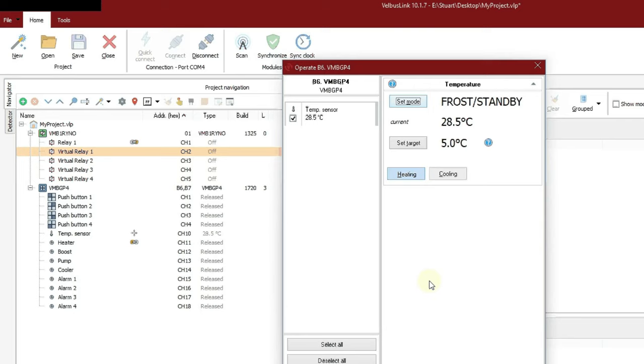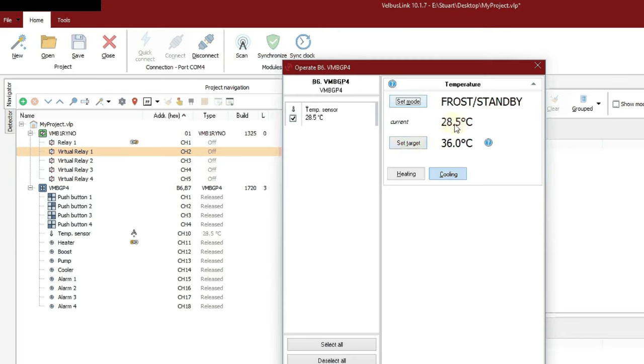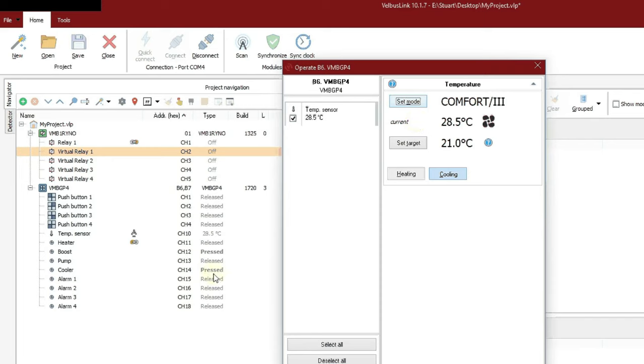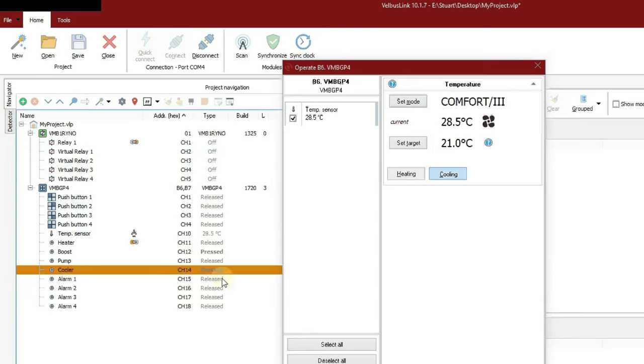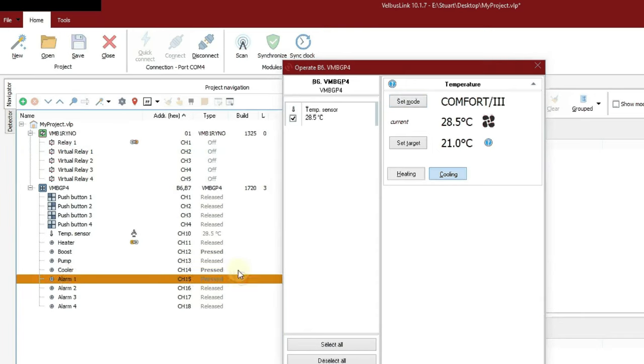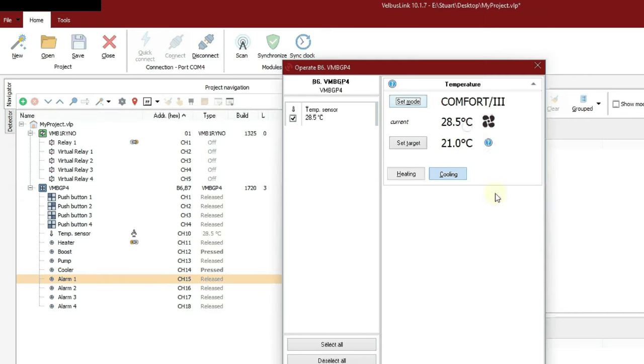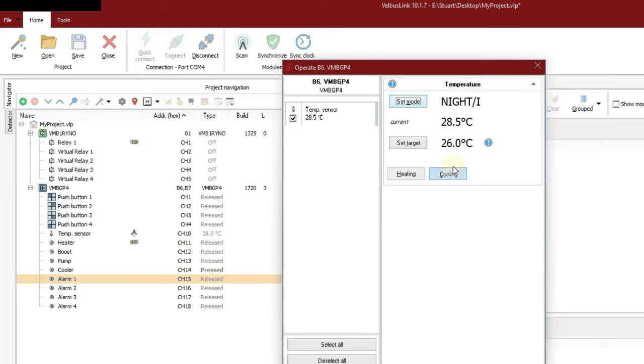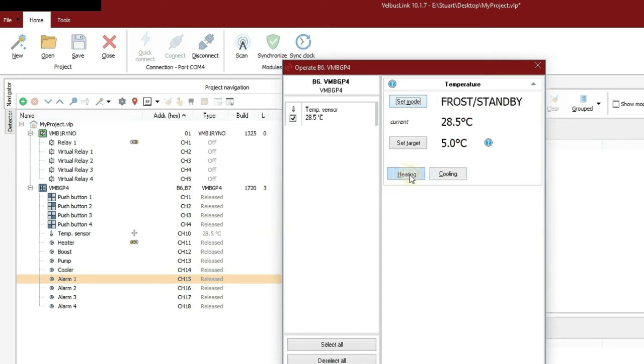Now the thermostats aren't just heaters. They are also for cooling. So if we were to do something with a cooling output, we could change the thermostat to cooling mode. And you see the target temperature is still 36. And the current temperature is 28.5. If we change the mode until it goes to something below 28 degrees, you'll see the cooler comes on as does the boost. And that means that our target temperature is more than 5 degrees away from the current temperature. Again that's fully adjustable within the configuration. Let's try the secondary layer of heating or cooling or air flow. And as we change around the modes, you can see it going on and off. As the target temperatures change. Good practice, we'll put it back to heating just so we don't confuse everybody.